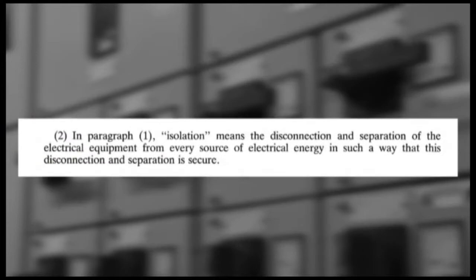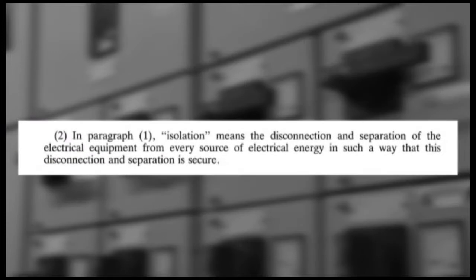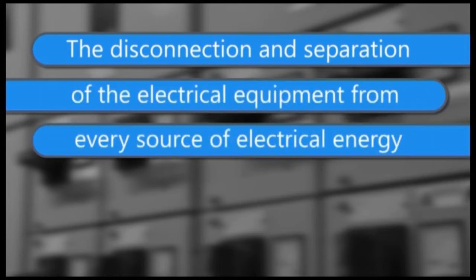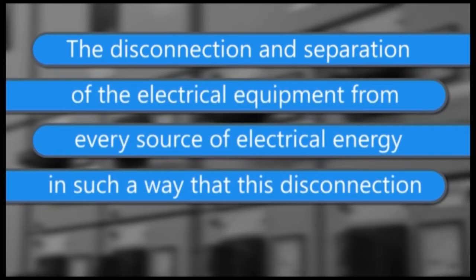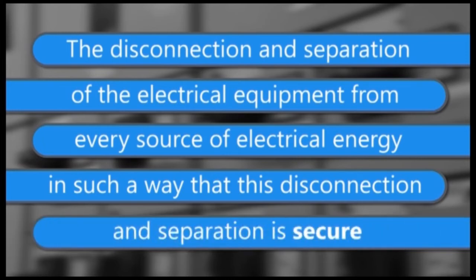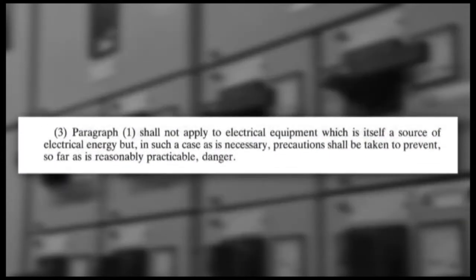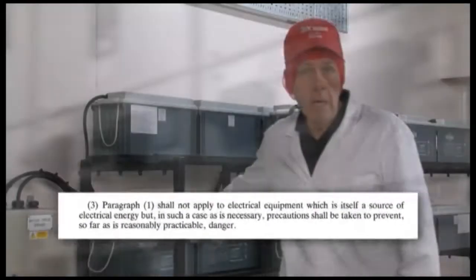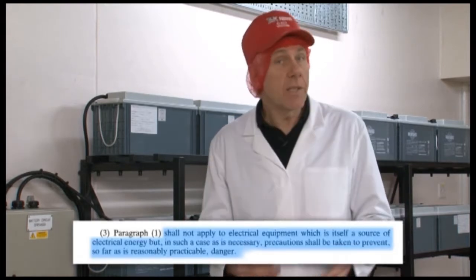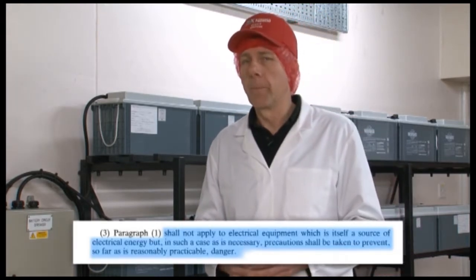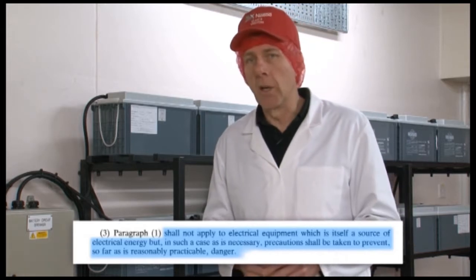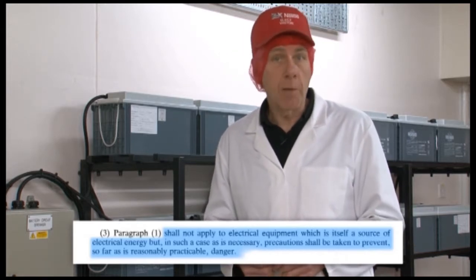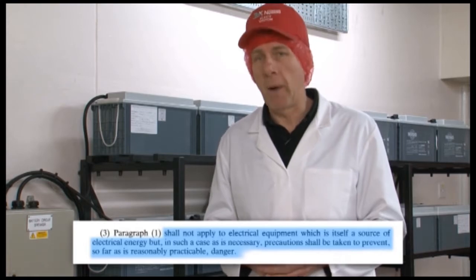Part 2 of the regulation, however, gives a clear legal definition of isolation: the disconnection and separation of the electrical equipment from every source of electrical energy in such a way that the disconnection and separation is secure. We'll be saying more about this when we look at Regulation 13. Part 3 exempts equipment such as generators and batteries from the regulation, including microgeneration equipment, since they're a source of energy in themselves. However, precautions must be taken when working on such sources of energy to prevent danger so far as is reasonably practicable.